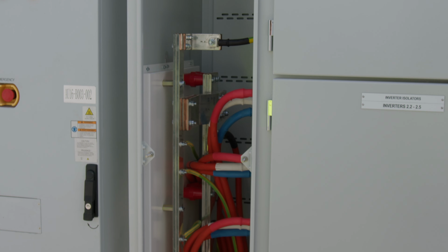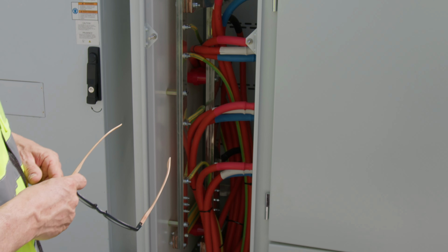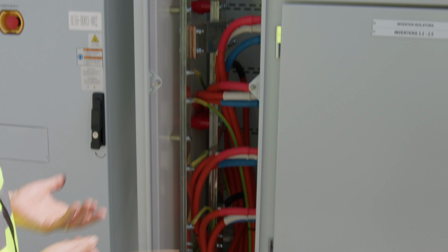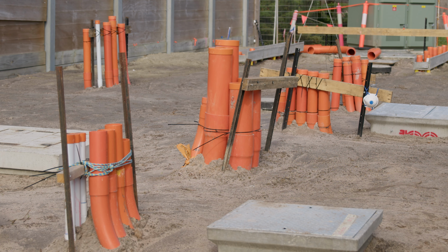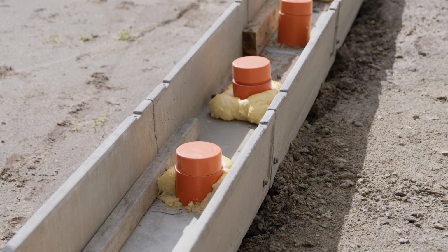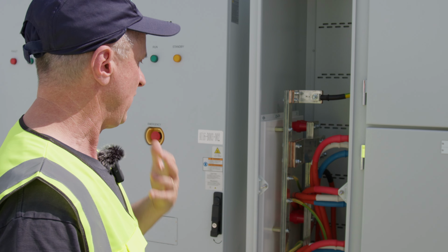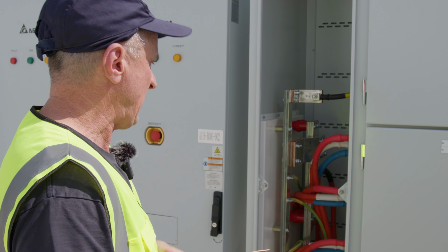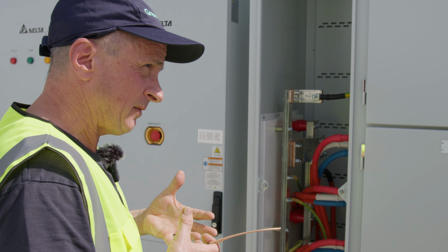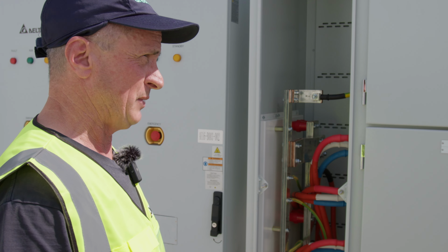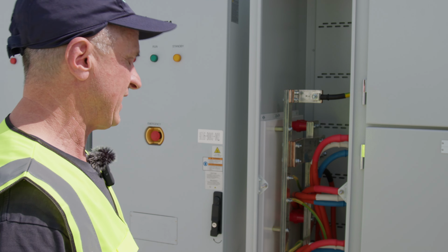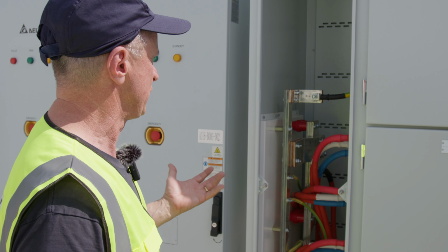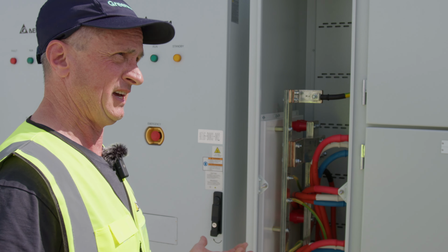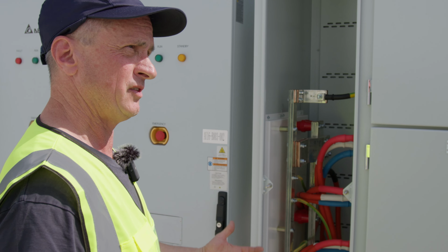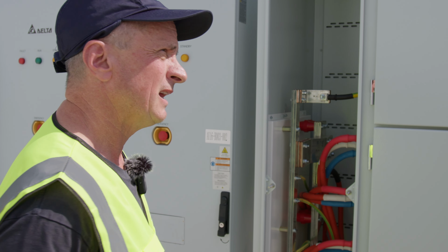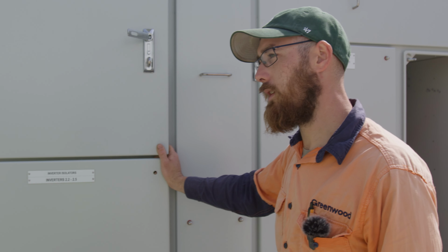So what Alex is talking about is, in some cases, the physical size of the cabling from an installation perspective, getting it through conduit, can really play havoc. So by going up to a sheath that has a higher temperature rating, the current carrying capacity can actually increase, because at the end of the day, copper is not going to melt unless it's subjected to some very hot temperatures, and the current carrying capacity of cable is due to the ability of the insulation to dissipate the heat. So this is 110 rated as opposed to a 90 degree. It's only an extra 20 degrees, but that makes a difference to our current carrying capacity to the point where we don't need to increase the cable size.